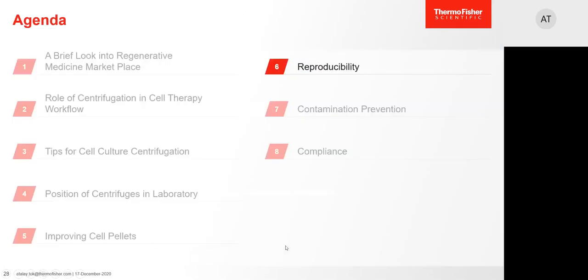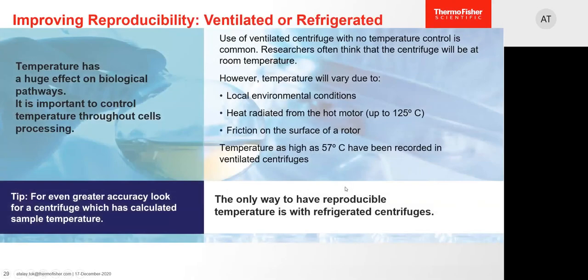Reproducibility is a critical factor that must be assured. One key feature that can help is refrigeration. While room temperature doesn't present risk for some applications, for most it does. Ventilated centrifuges can heat up to very high temperatures that can risk your experimental success. Factors such as how many centrifuges are in the laboratory, and how often and how long they are used, are important — especially for ventilated units. With a refrigerated centrifuge, you have the tools to minimize and control such temperature rises.